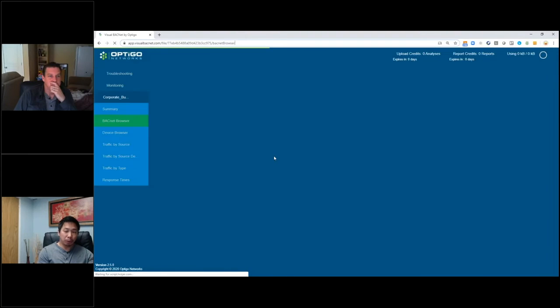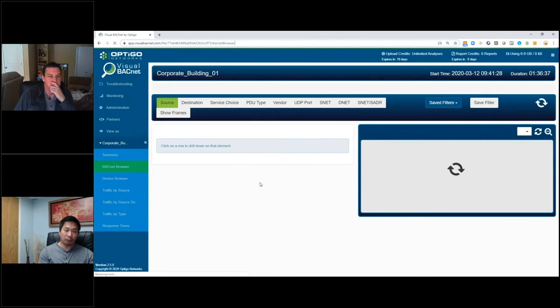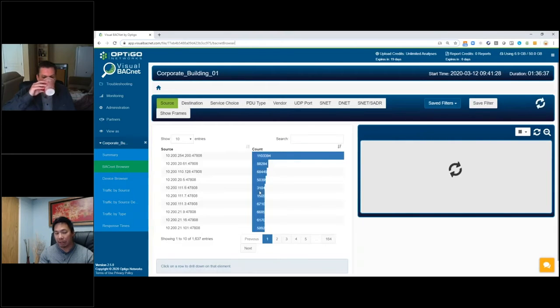And again, the other thing to keep in mind here is that all OS-based computing has limited processing power. So let's take, for example, a Raspberry Pi. If we load a BACnet stack on a Raspberry Pi, it could probably handle about 1,000 packets a minute without choking too much. So very often when we say the network is slow, it's not necessarily the network itself that's slow, it's that the devices that are networked are getting so many messages that they cannot process all of them. And that's why it's so very important to turn down as much broadcast as possible, to leave room for processing the messages that are meant for that device.